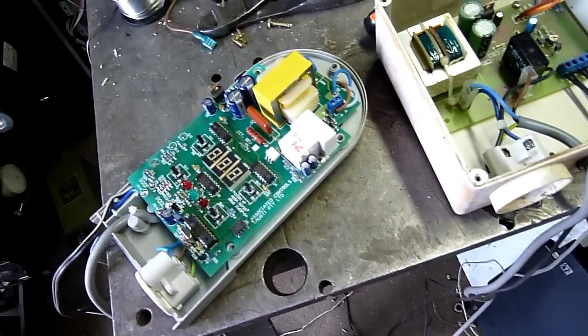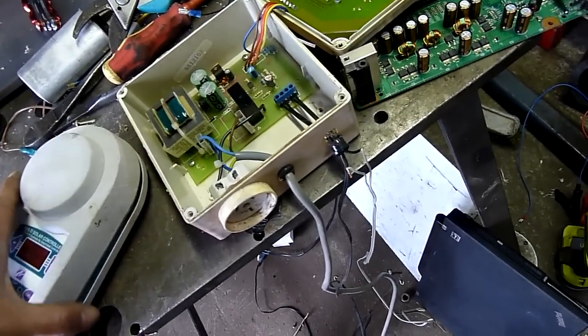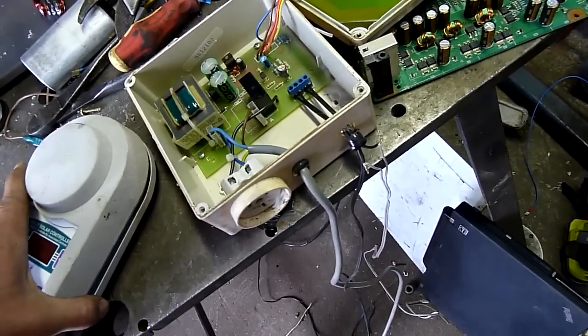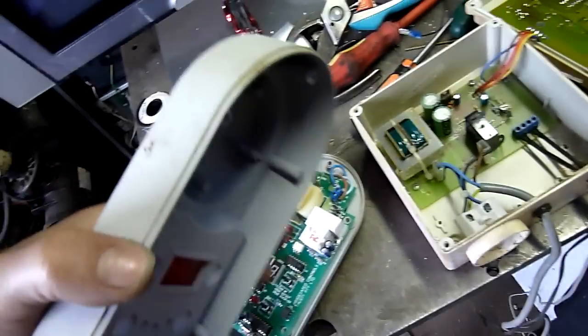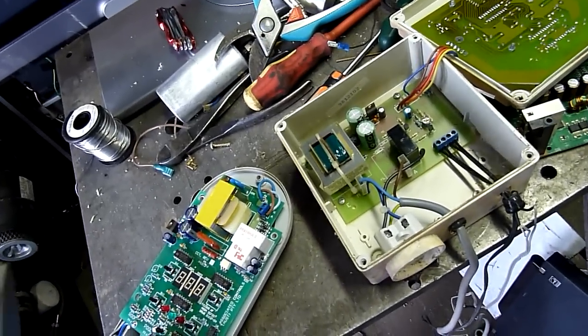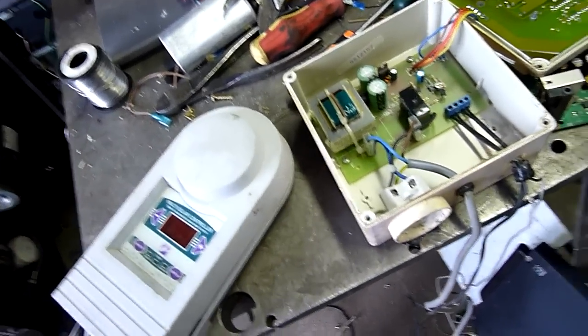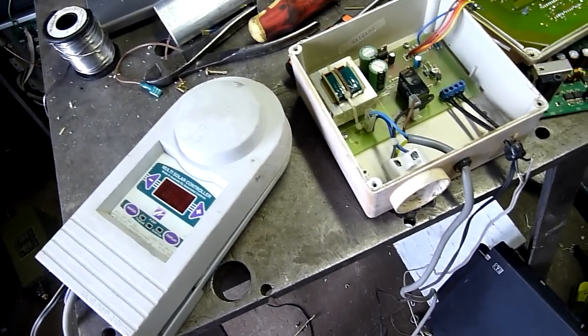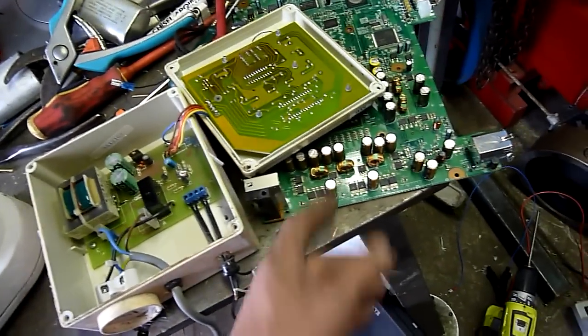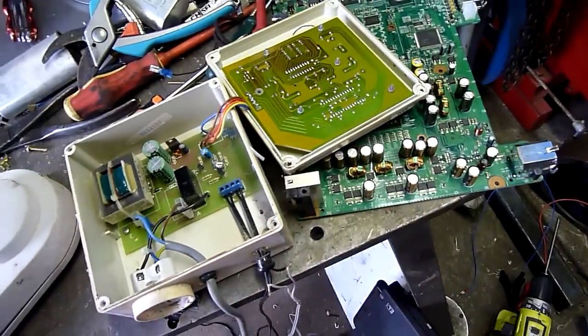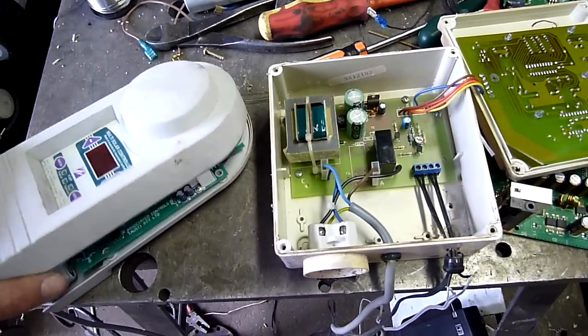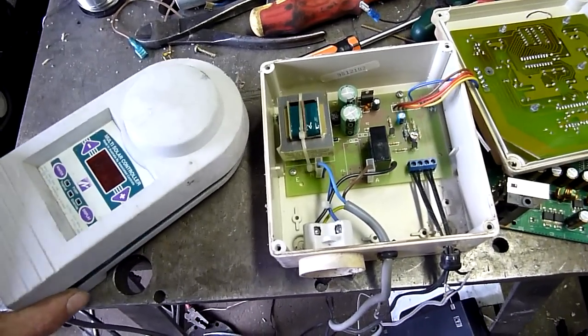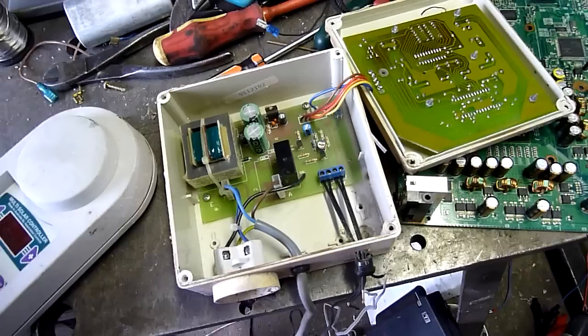One of the failure modes of the ones that work is that the casings, originally the way they were designed, were they were designed like that, with an overlap, but no gasket, and they'd leak water. So, I was forever throwing them out because the power supply was just blown to pieces. And yeah, these ones here seem to be a lot more robust.